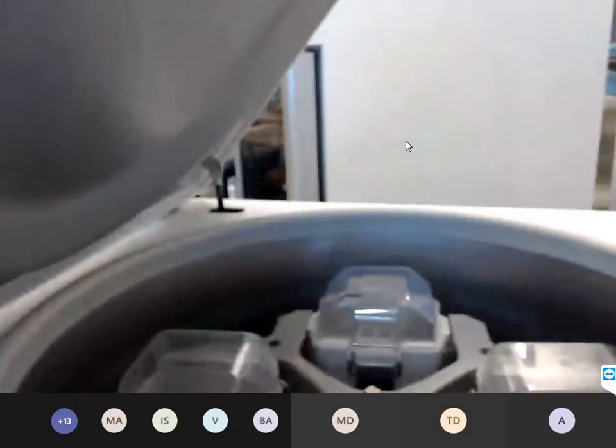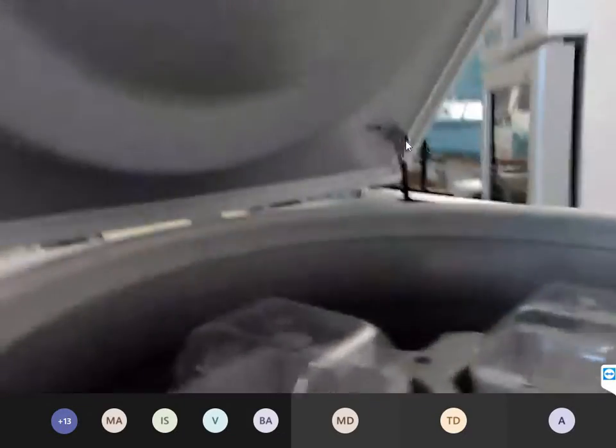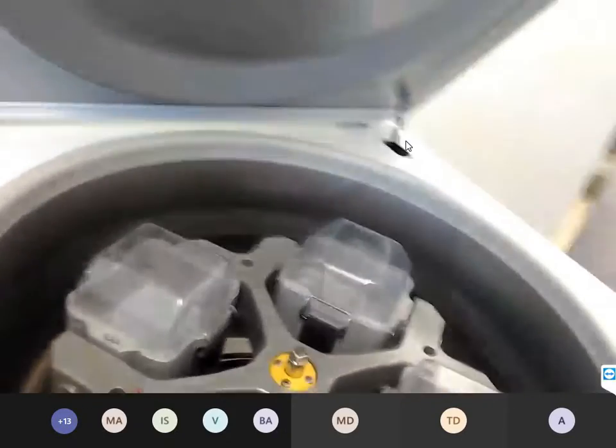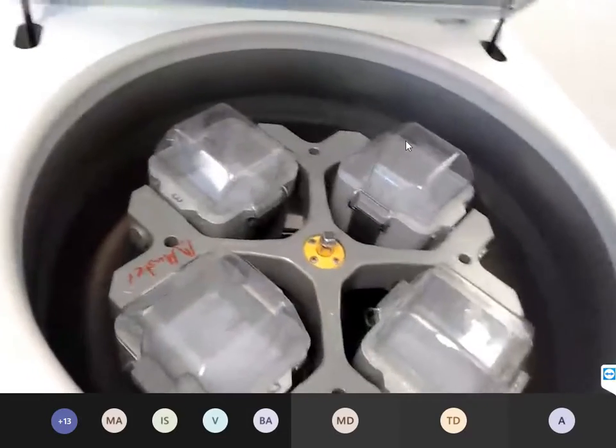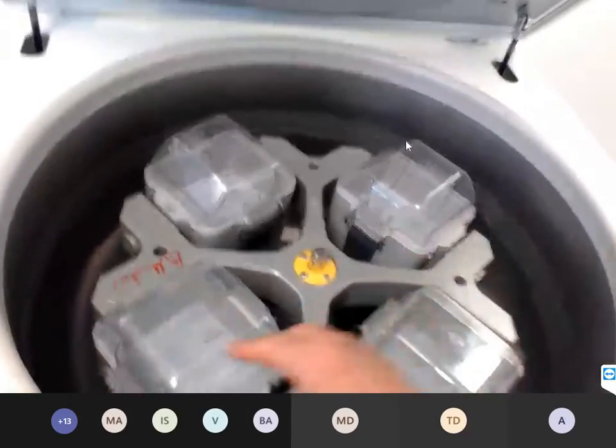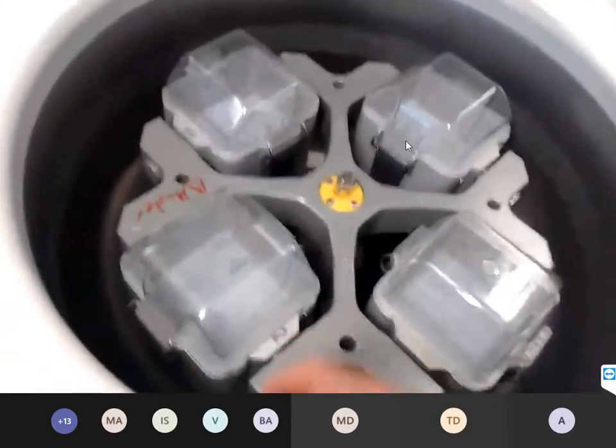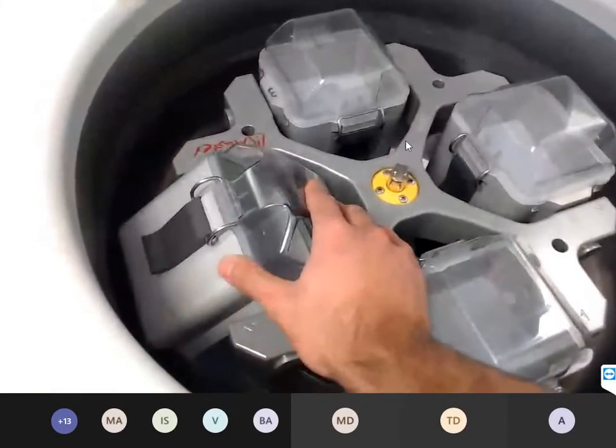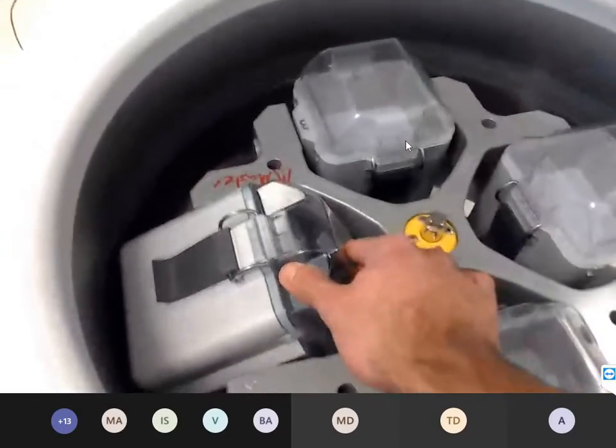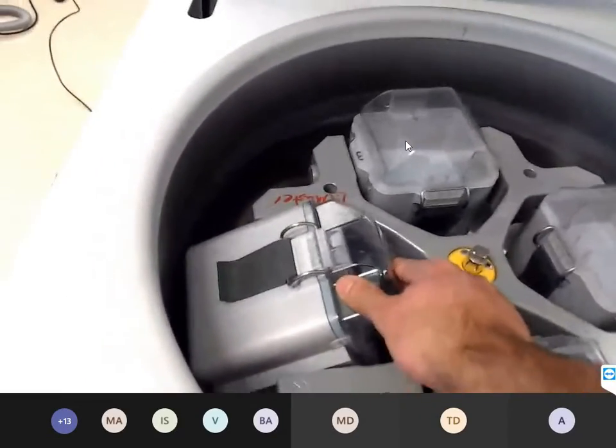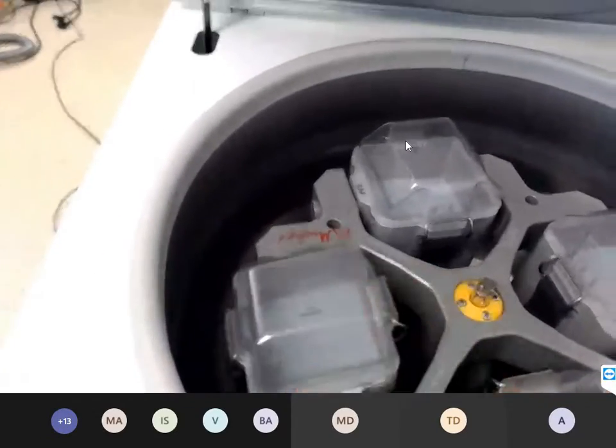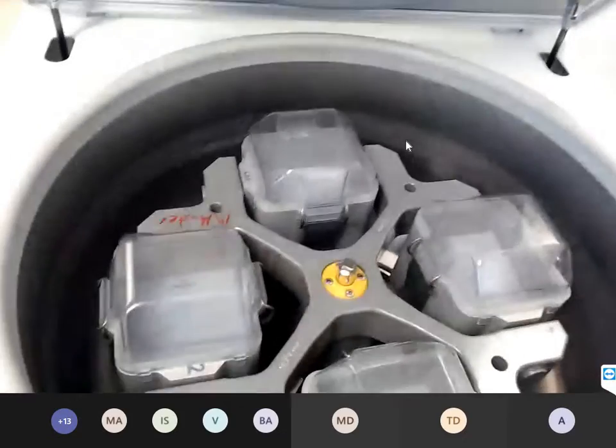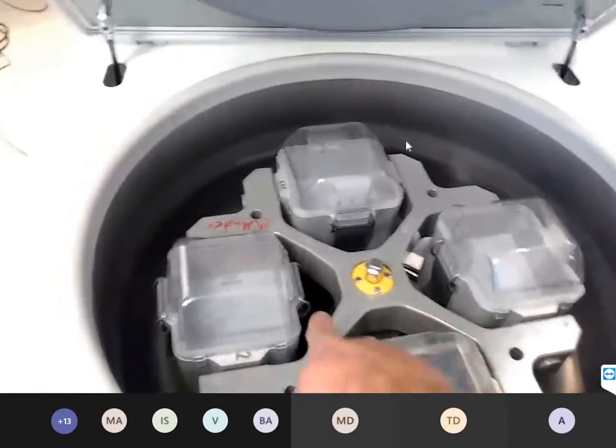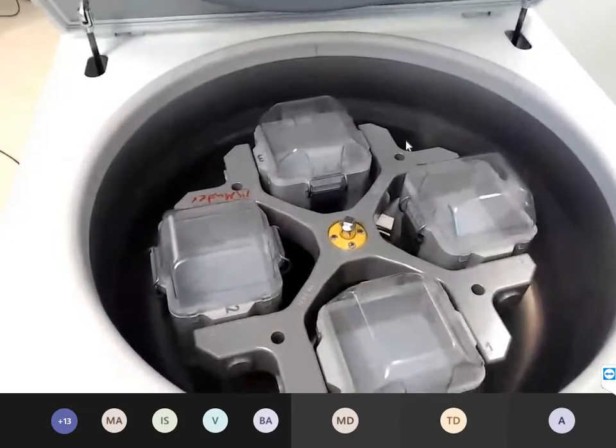What is important? In case of a replacement of the motor, you have to set the middle position of the motor, because we have a tolerance. If you don't set the motor position, in worst cases, the buckets cannot swing out smoothly. They touch the chamber, and in worst case, you get a crash. It's very important to set the middle position in case of a replacement of the motor itself.